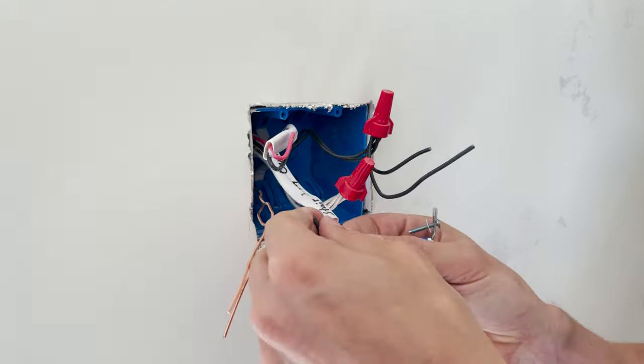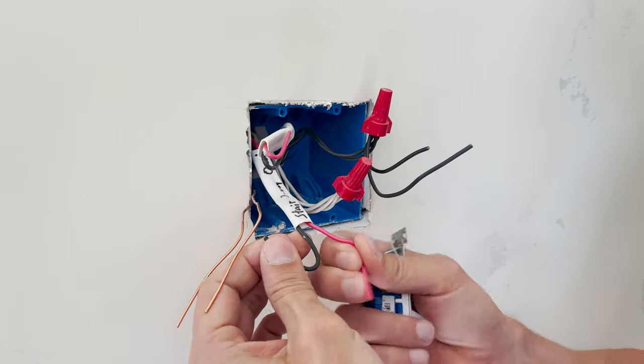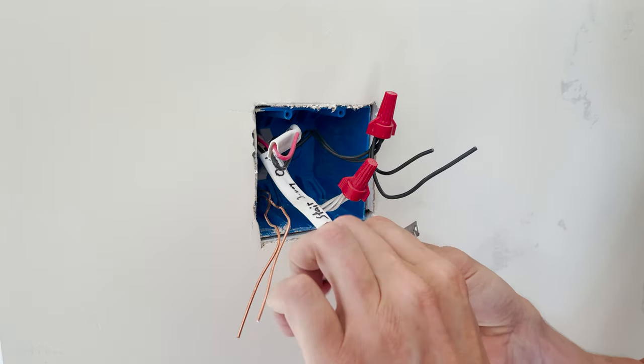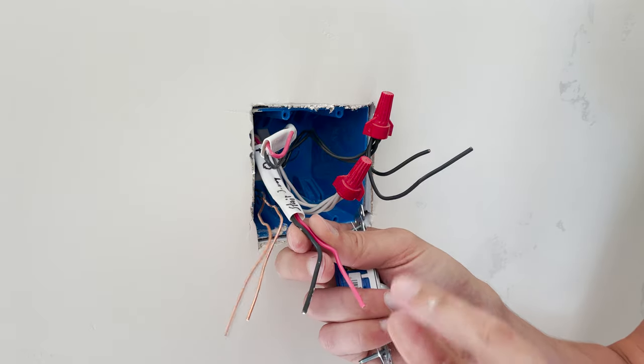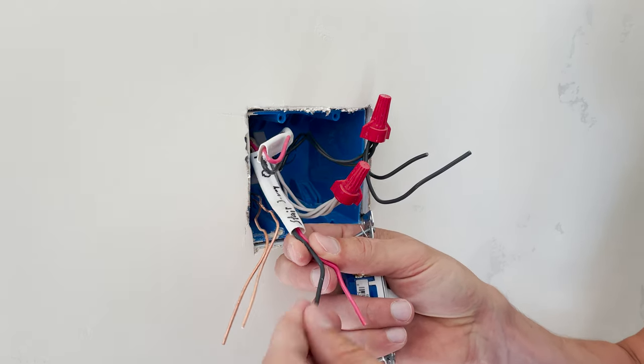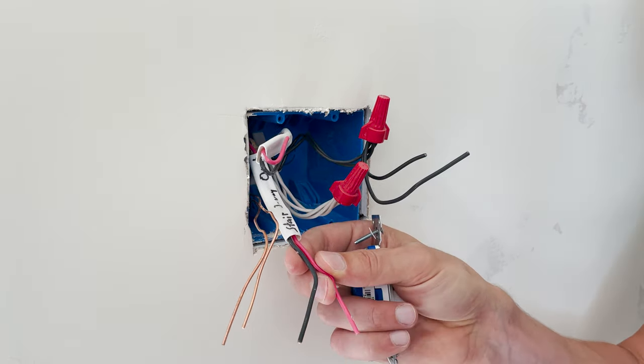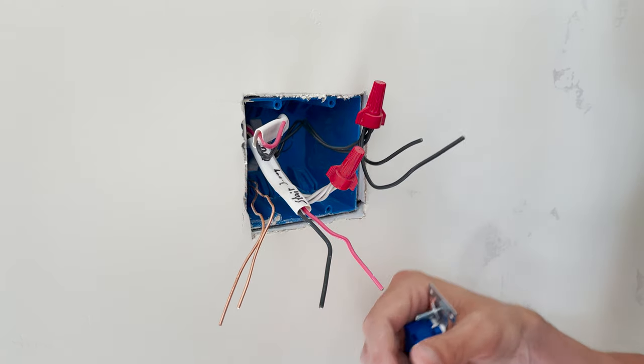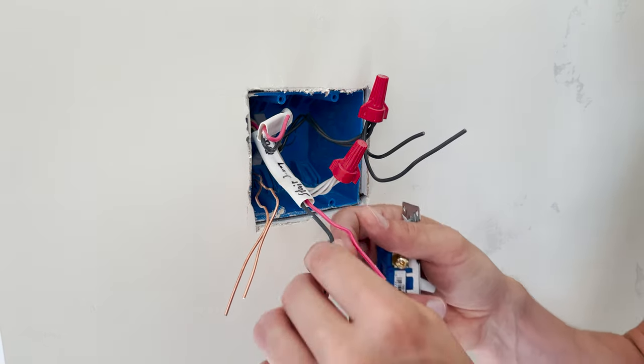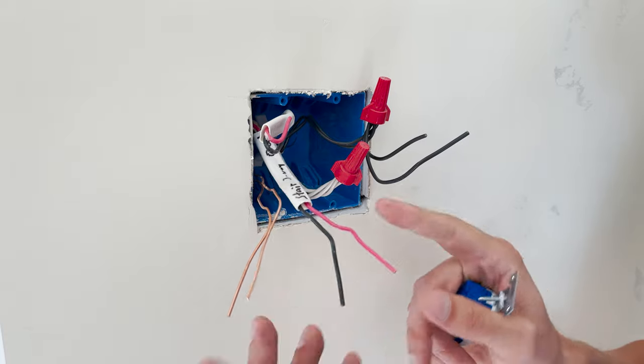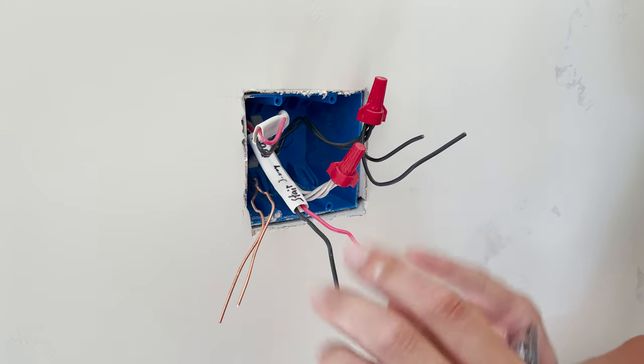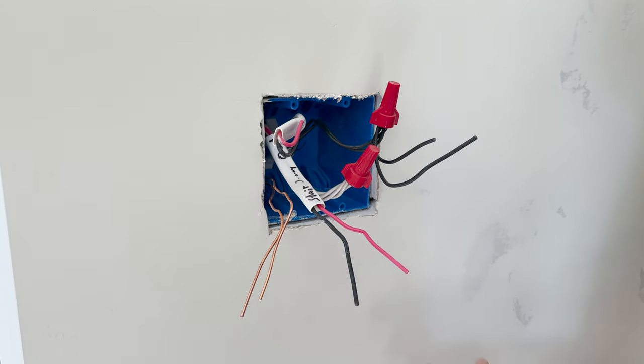And as you can see, we have a red wire here. And that red wire is something that you get with your 14-3 in this case. This is that third conductor. And as I've mentioned in other videos, red can indicate a lot of different things: communication line, an extra wire. If you're doing a 240-volt system, this is how you get your different voltages. However, in this case, we are using it as the traveler wire.